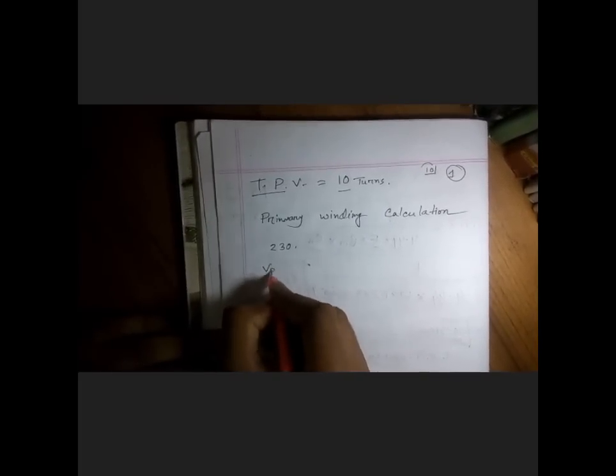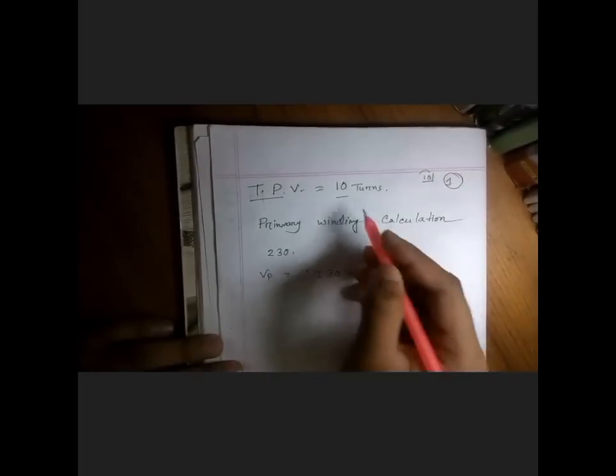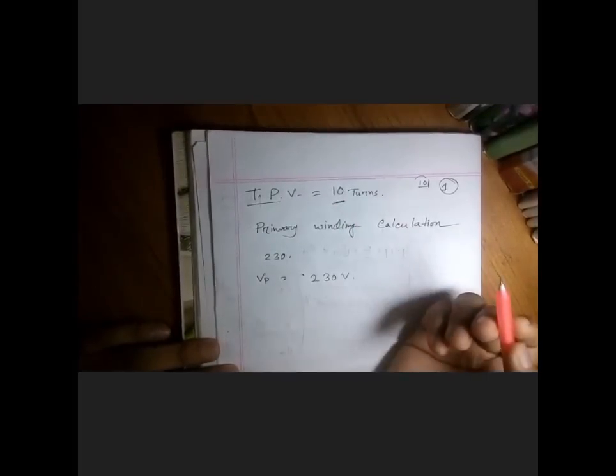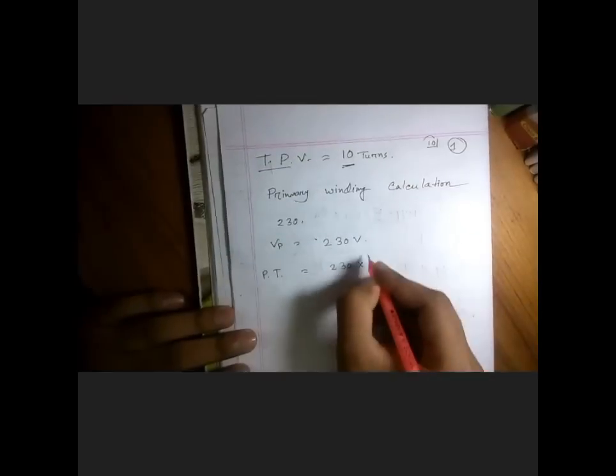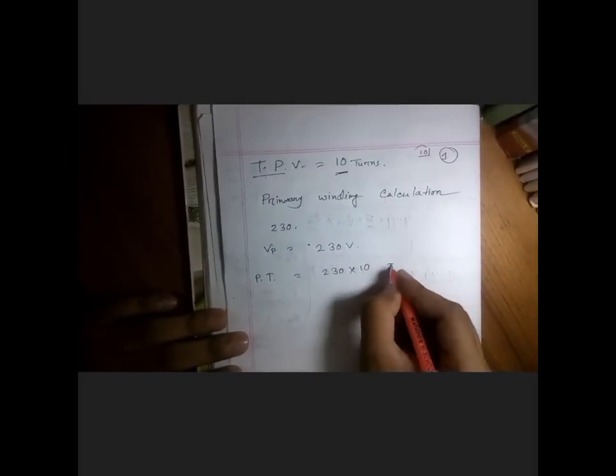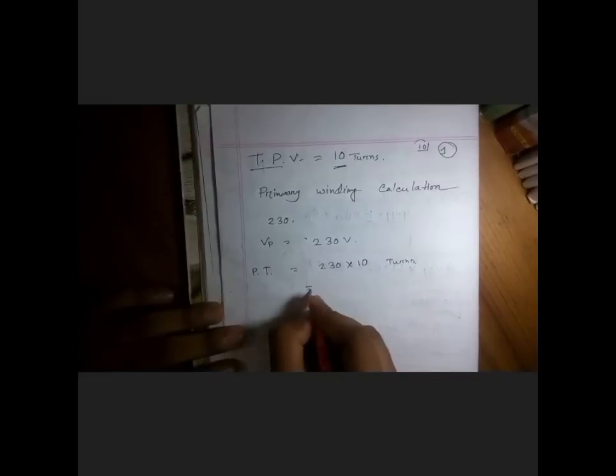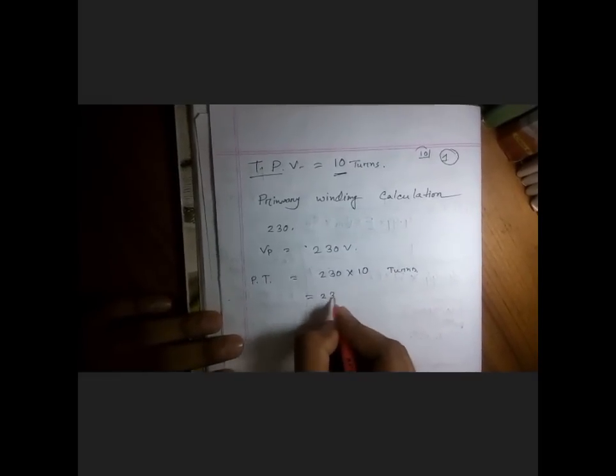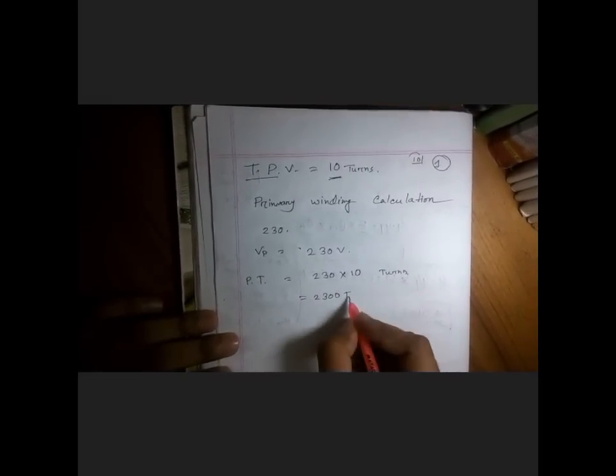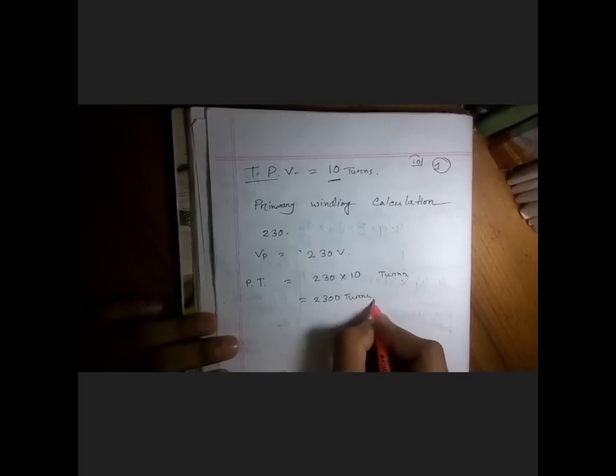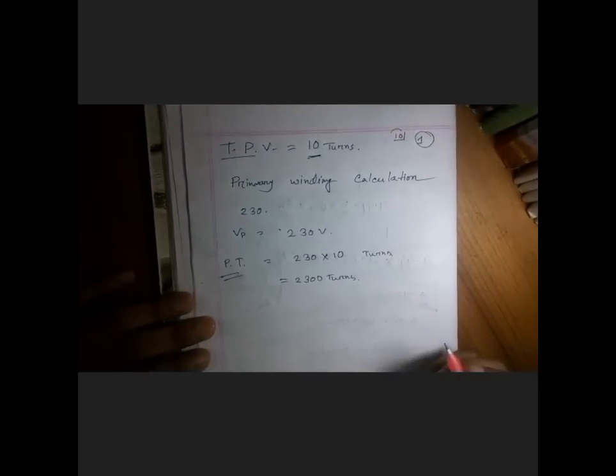Then so Vp equal to 230 volt and turns per volt equal to 10 turns. So primary turns should be 230 into 10, okay turns. So it's about 2300, two thousand three hundred turns for primary winding.